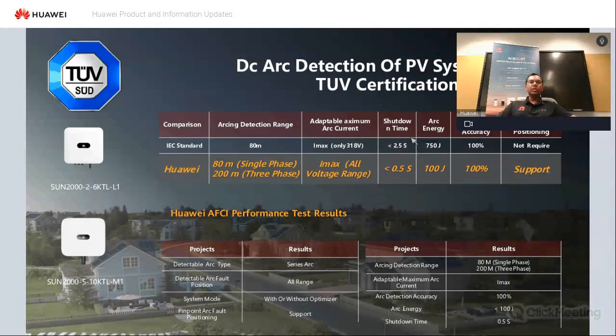Industry standard for an inverter shutdown in case of an arc fault is 2.5 seconds. That's an international standard. Huawei inverters shut down in less than half a second if any arc fault is detected. And we're talking up to 80 meters for single phase and 200 meters for three phase. The main reason why most of the third-party inverters have this off by default is because of false alarms, because it is quite hard to detect a real arc fault and not a false one. So that's the reason they have it off. Huawei has it on by default as well. So that's the confidence that we have in our proprietary algorithms.